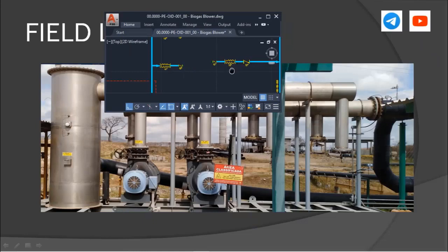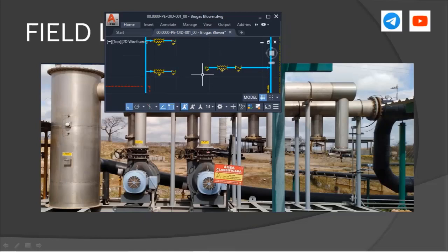And in the discharge, we also don't have the isolation valve, 12 inches isolation valve, neither the expansion joint nor the check valve. The check valve in the existing plant is this piece here. You can see that it has a flange here and a flange here, so it is the check valve. However, in the field we don't have those fittings, piping fittings. So during our project development, we need to point that out and consider it in the cost of the project.